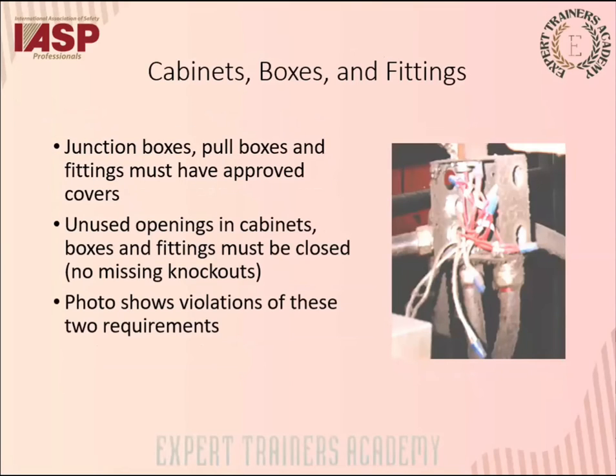Cabinet boxes and fittings. The junction boxes which you use or the pull boxes which you use, the electrical fittings that you use, must have approved covers. And unused openings in cabinets, boxes and fittings must be closed. So there's a photo which shows a violation of these 2 requirements, which is not protected at all.